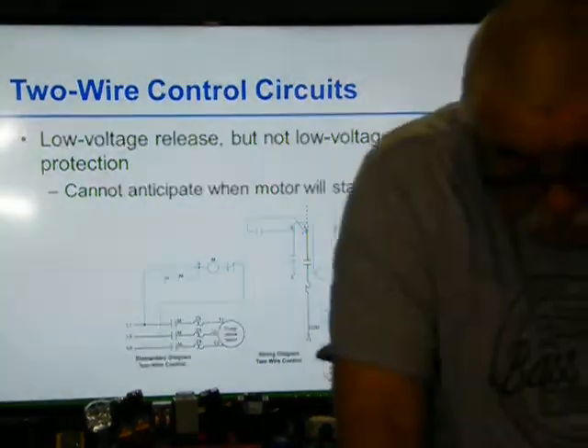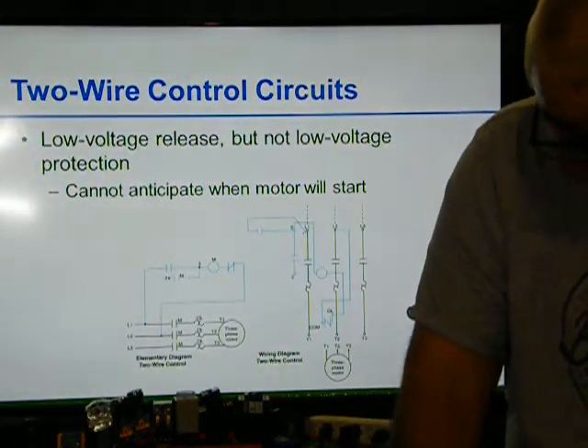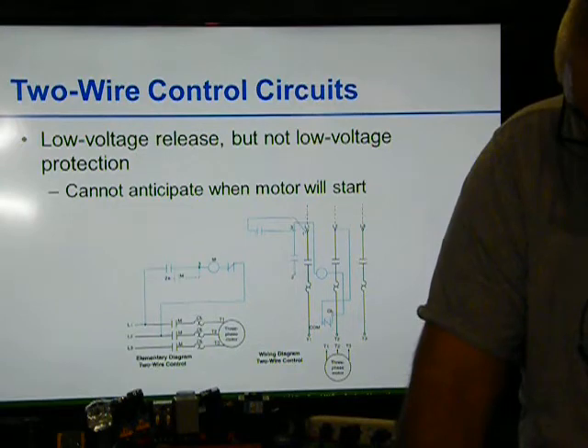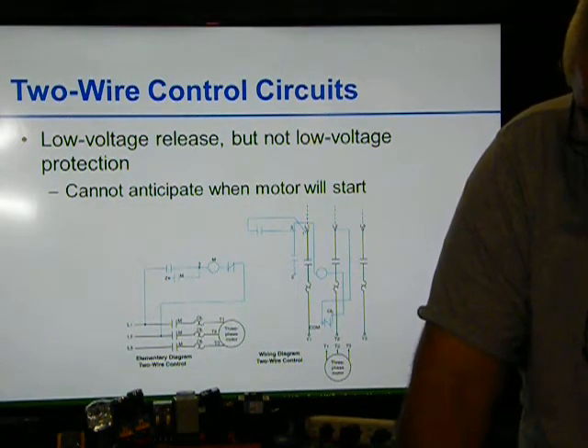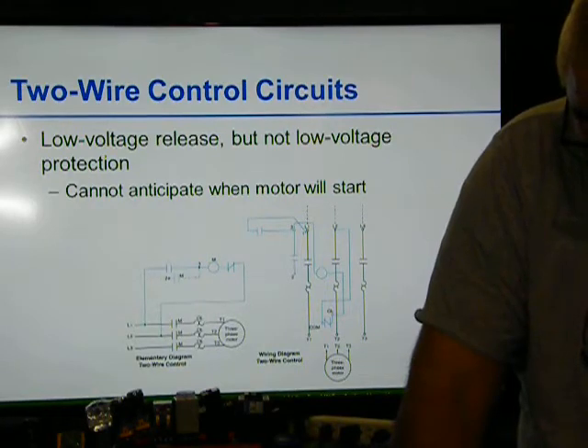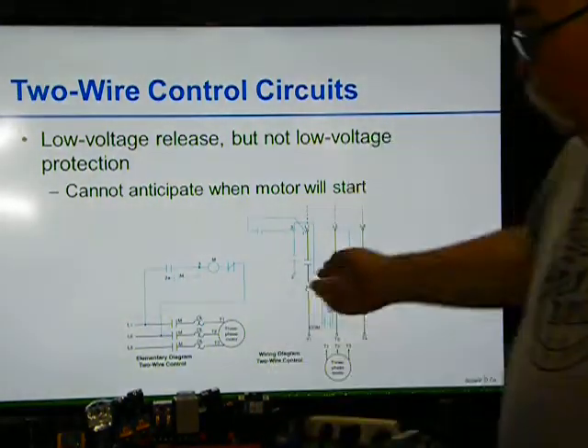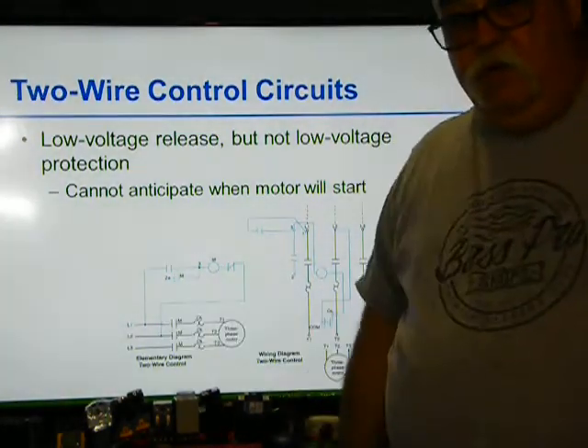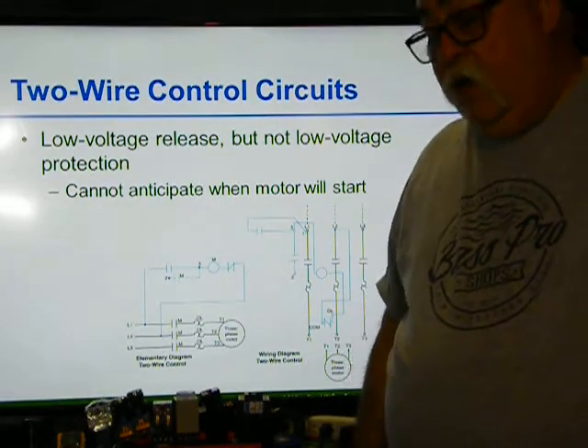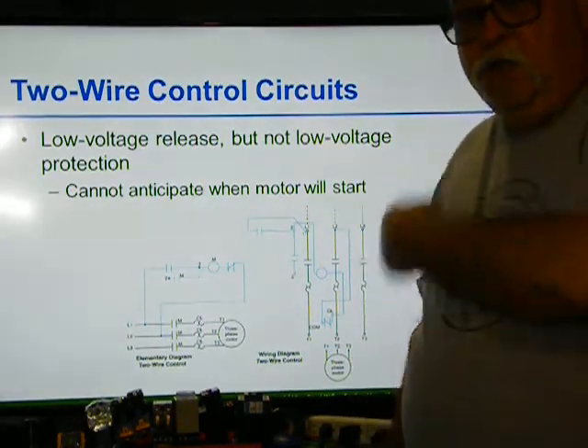Don't use these two-wire circuits. When power is lost, the control circuit contacts will release, stopping the motor. When power returns, the coil is re-energized, starting the motor. Low voltage protection is missing, so there's no way to anticipate when the motor will start. Therefore, extreme caution must be exercised when servicing a two-wire circuit. When you're working on one of these circuits, you better make sure you turn that breaker off. Lock it out, tag it out, make sure nobody can turn it back on you.